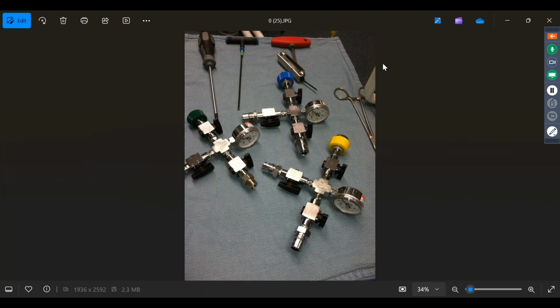When I'm checking my gas alarms and stuff like that, I can isolate the anesthesia machine from the wall, and then I can bleed off the gas in the line, and I can see the pressures drop. And then when the pressures drop to certain levels, I can see my alarms trigger for low gas alarms. Those are like one of the best things you need to build for doing this job.